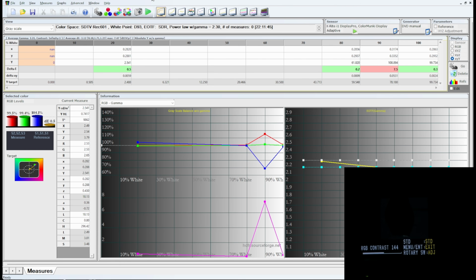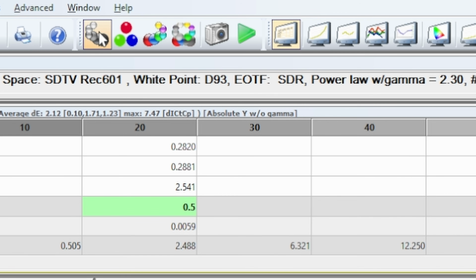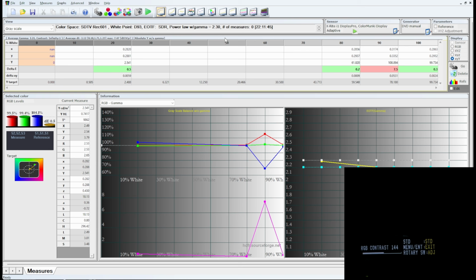Now we want to go ahead and check all of the levels and make sure that the entire test is accurate, that our full sweep is accurate. So we're going to do a full gray sweep. What that means is that we're going to go down to 10 IRE, we're going to press this button right here, and it's going to take us through one at a time every single one of these steps. Now 90 is way off because I touched it by accident earlier. Yours is probably still going to be blank, so just ignore that.